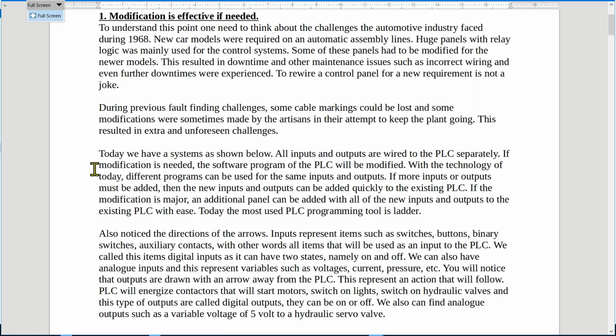Now today we have a system as shown below, and I will show it in the next couple of seconds. All inputs and outputs are wired to a PLC separately. Now the benefit is, if modification is needed, the software program of the PLC will be modified. With the technology of today, different programs can be used for the same inputs and outputs. If more inputs or outputs must be added to an existing system, then the new inputs and outputs can be added quickly to the existing PLC. If the modification is of a major concern, even an additional panel can be added with all of the new inputs and outputs to the existing PLC with ease.